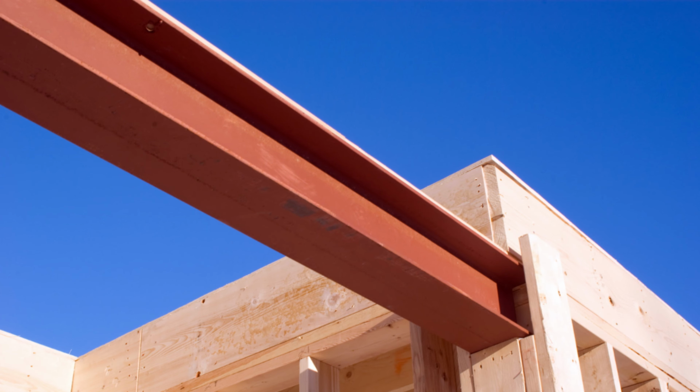The next one is what's called thermal bridges, and removal of thermal bridges. An example of this is where you've got a steel beam that's supporting your floor internally, that maybe then goes outside as well and supports a balcony externally on the building. So that is a metal element, a thermal conductor that connects the inside structure to the outside structure. And being a thermal conductor, it's actually drawing energy through the member length itself. So we want to try and avoid that, so that we have structure inside the house and structure outside the house, and those two are separated in some way thermally, so that there is no bridge between the two elements, and therefore energy passing from inside to outside doesn't happen.